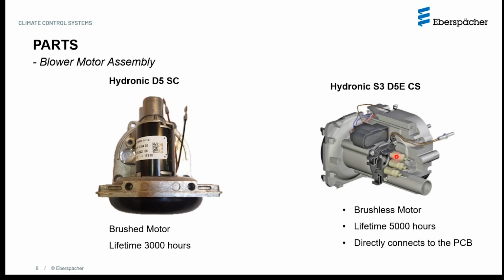Now, the whole purpose of tearing down a heater has to be first diagnosed correctly. You do not tear apart a heater just because you think something may be wrong. You will always do the diagnostics. We are going to do a brief demo on the diagnostics later on in the webinar. And based on your diagnostic results, the fault codes, etc., once you have verified that yes, you have a component that has failed, only then will you proceed with the teardown of the heater. And of course, when you do that, you always will have a spare part available. So for example, if you want to replace a fan assembly, or a sensor assembly, or the glow pin assembly, each of those parts will contain the cover for the motor. It's included in the scope of supply. That means anytime you tear apart the heater to replace any of those parts, you'll also replace the cover for the motor.